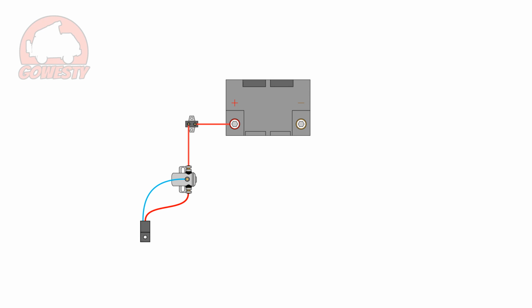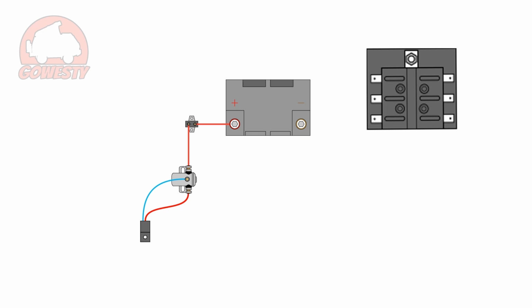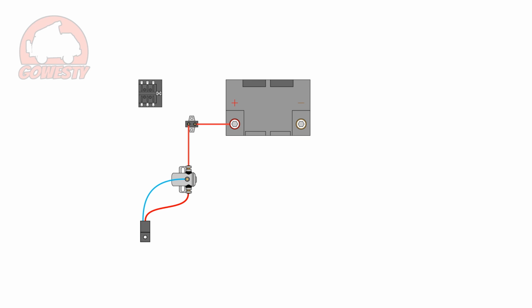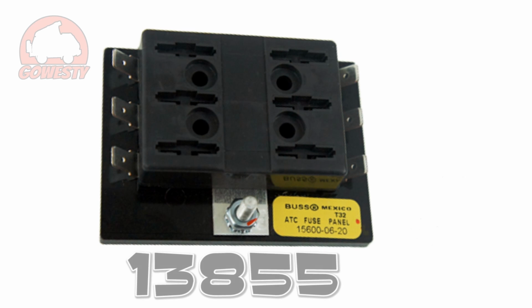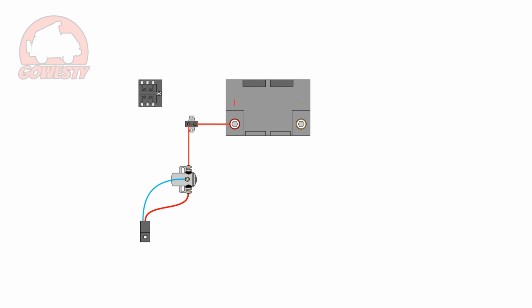While using the provided wire with an inline fuse works perfectly, another option is to use an auxiliary fuse panel to control the distribution of power from the auxiliary battery. These can be found in a variety of sizes and fuse types, but we've had the best results with the 6-fuse model we sell on our website, part number 13855. These can be easily installed near the isolator. Simply add a wire to the circuit breaker post and then connect it to the fuse panel post. This block can now be used as a protected power source for components powered by the auxiliary battery, like the camping equipment in the van.